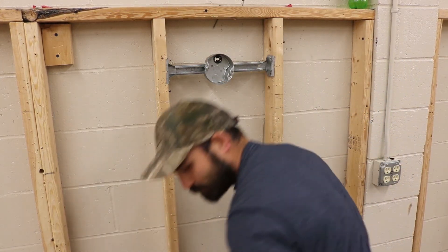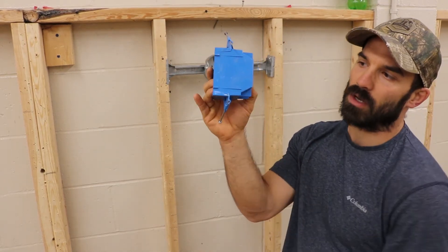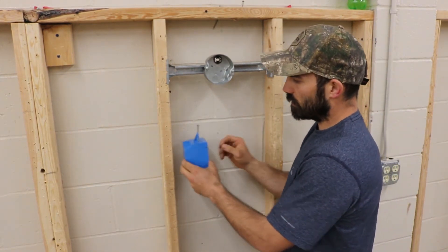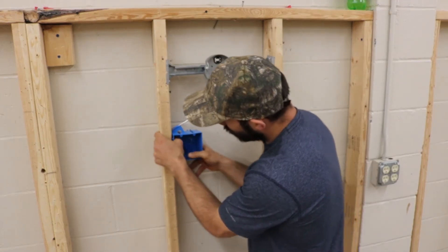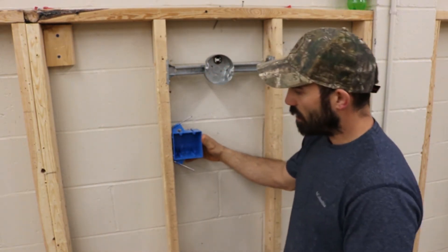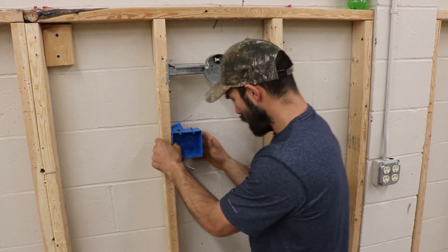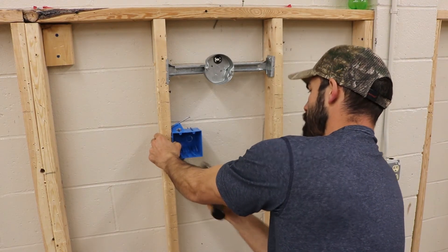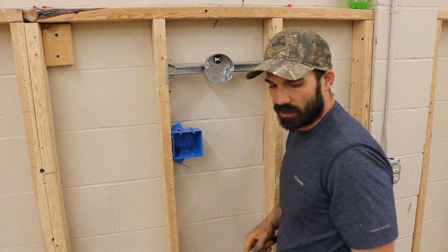The next box to mount is a simple nail-on box. Make sure those two tabs are sticking out past your wood studs. You're going to mount these boxes at 54 inches. The best way is to put your box on there, line it up at the bottom, and mark the bottom of the box — there's a center line you can mark. Make sure the tabs are sticking out past your stud, then use a hammer, get it set on each side, and finish driving those nails in.